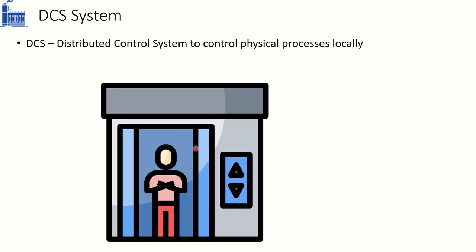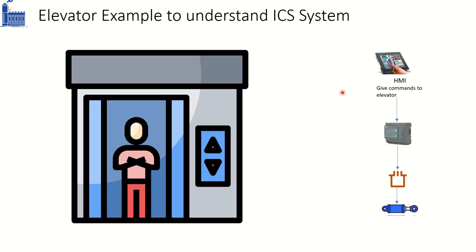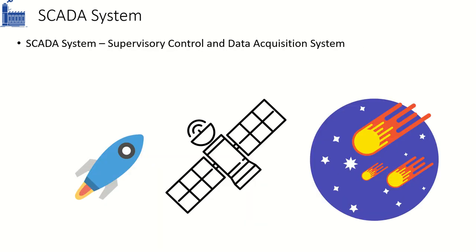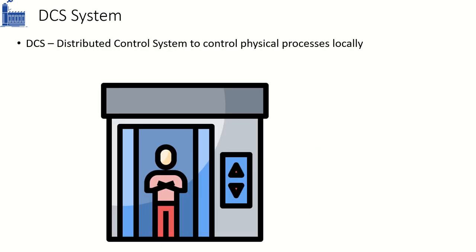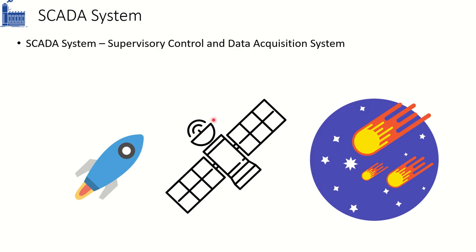A distributed control system which usually works just locally will not need to have a remote transmission unit, because there the information is flowing just locally - you are controlling a physical process that is just happening locally. That is the reason in a DCS you would not see a remote transmission unit usually, but in a SCADA, remote transmission units will be required because you will be controlling a physical process that is far far away.